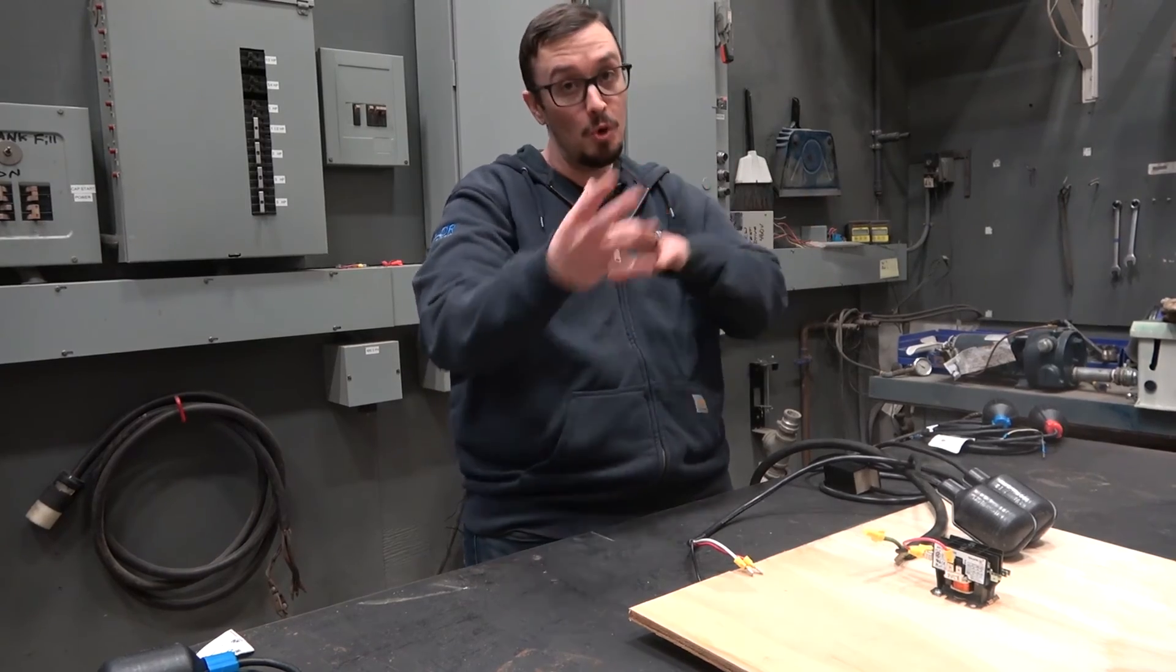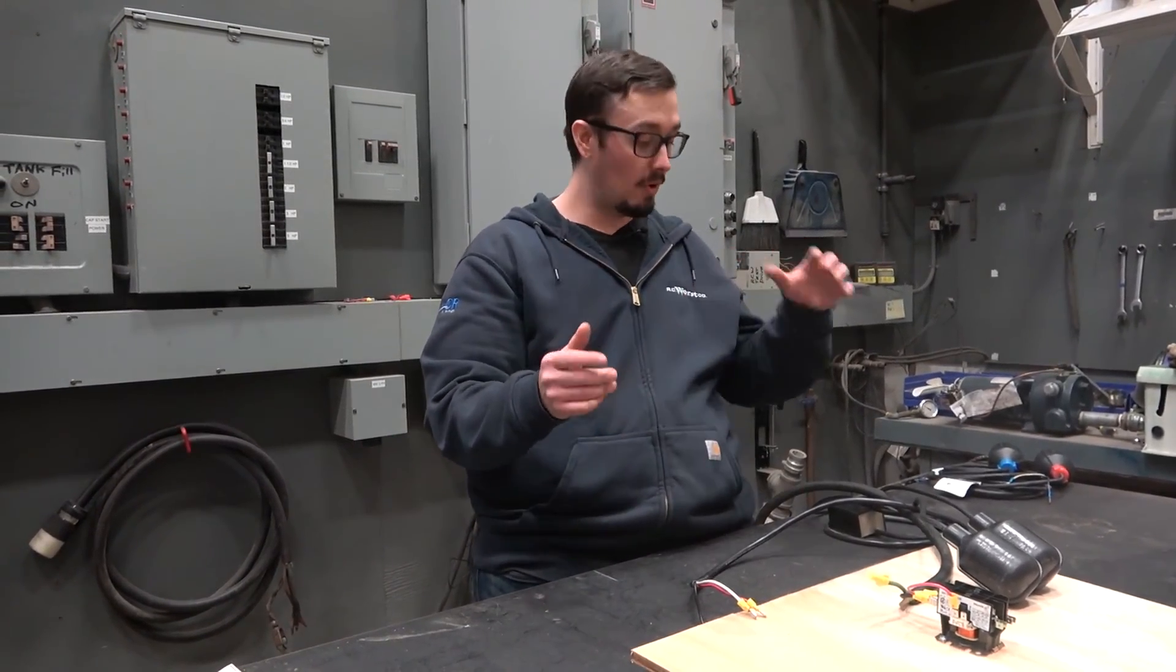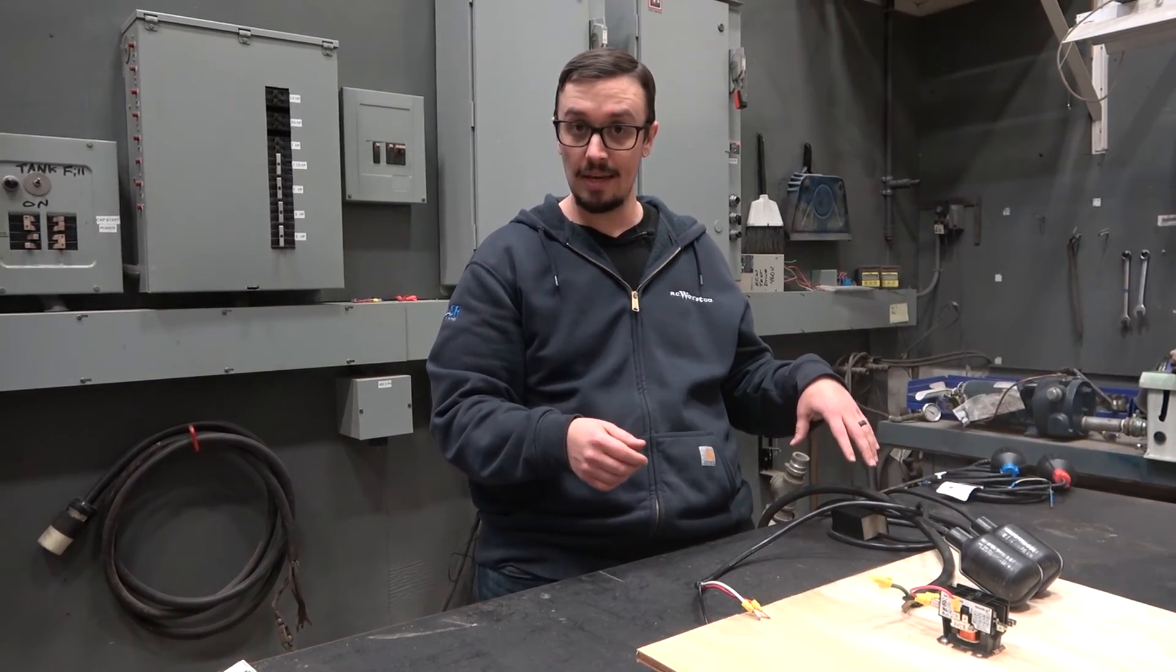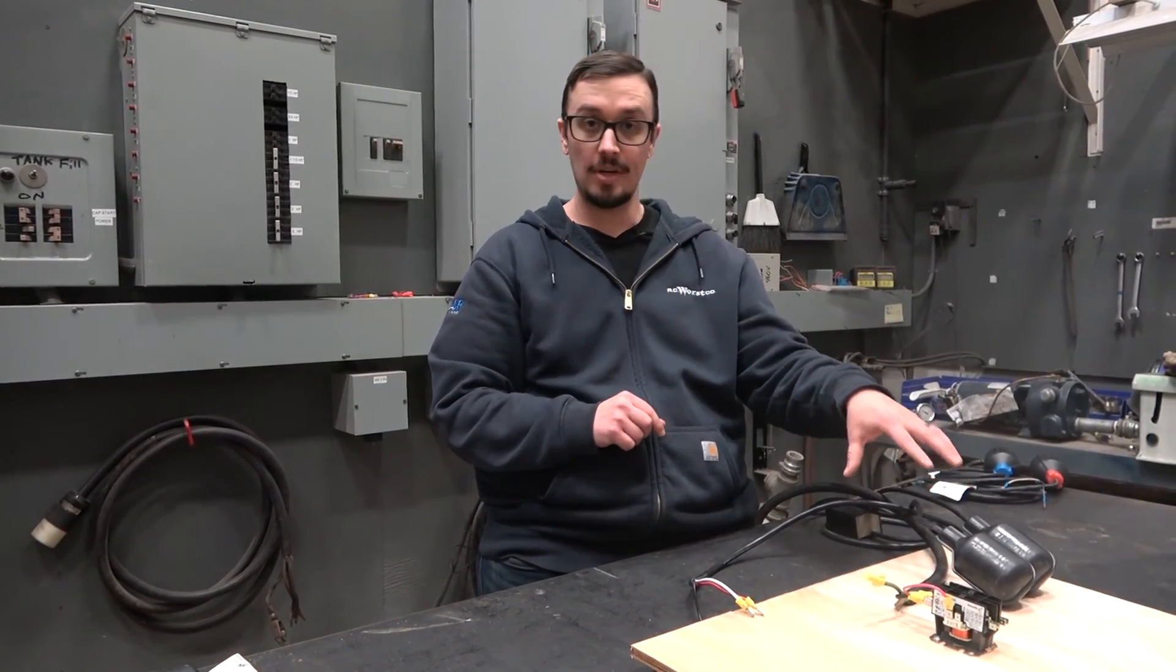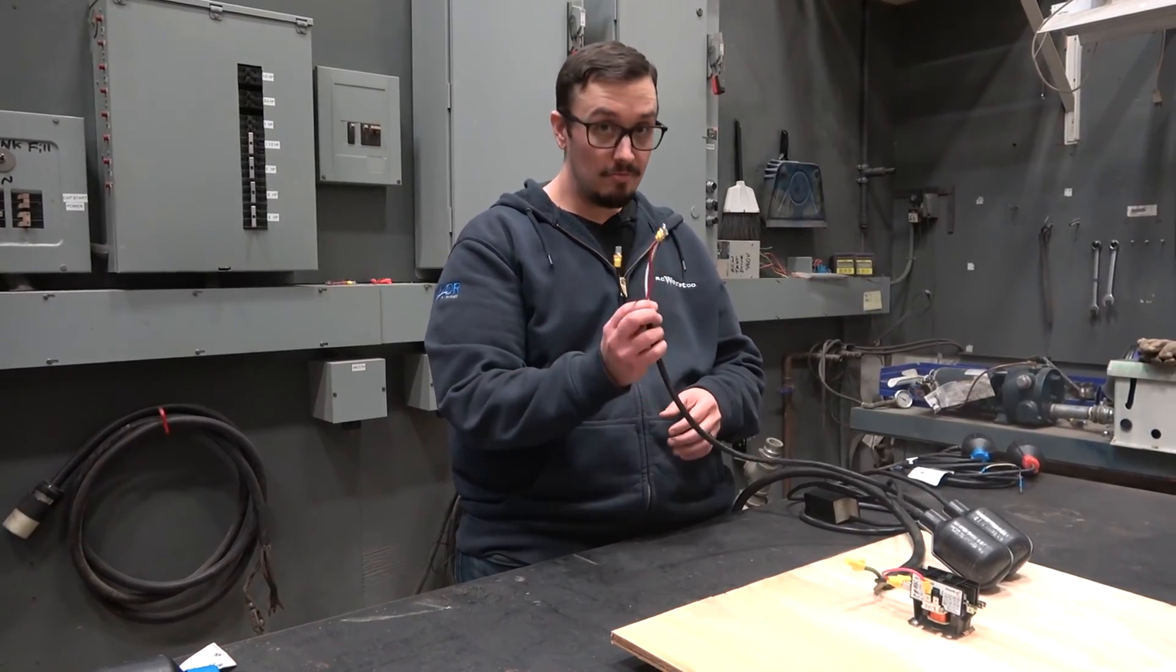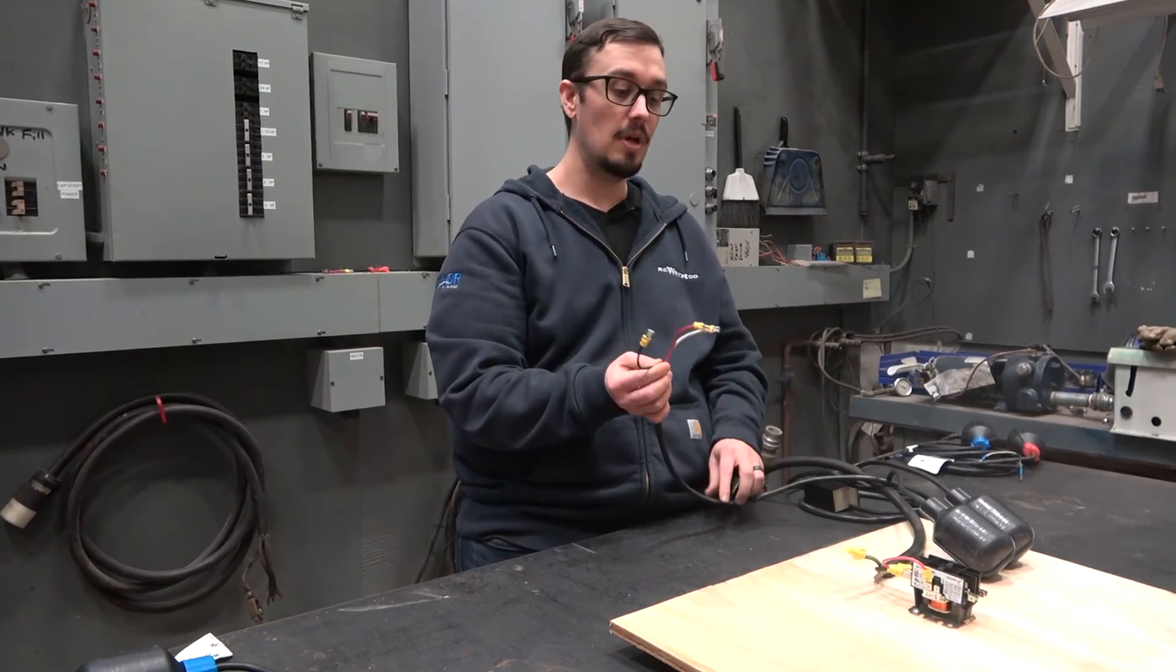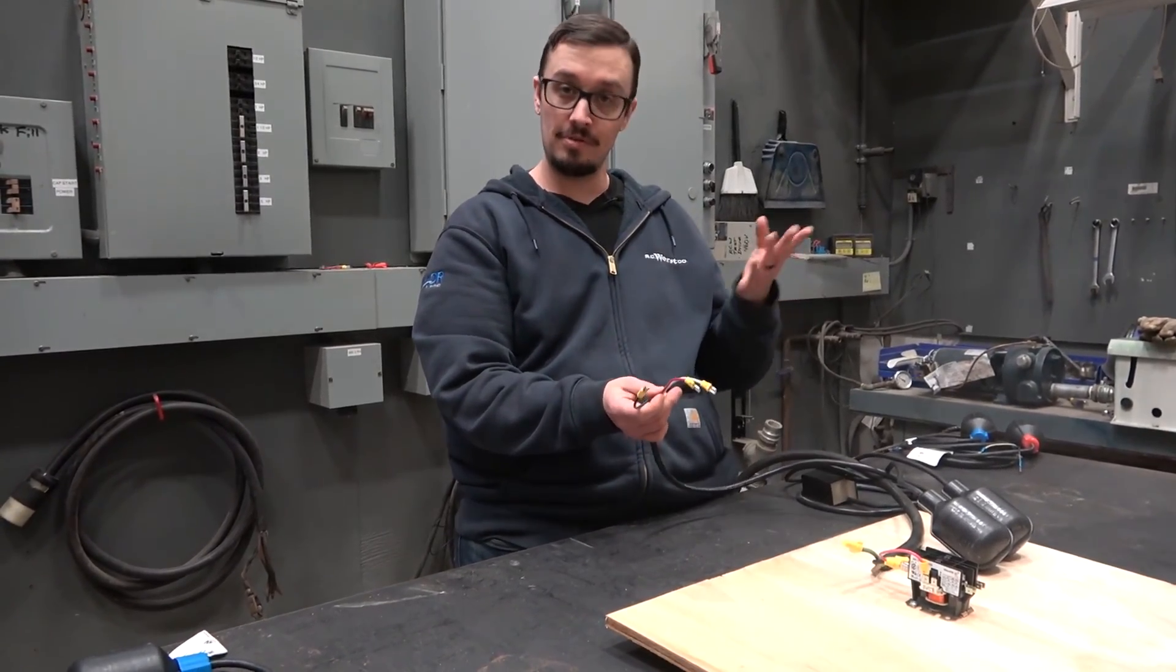We're doing a single float setup as well as two floats, not to be confused with a double float, whereas the double float has a built-in relay that creates a holding circuit within the action of the floats itself, which is why double float switches have three wires instead of your typical two. So the wiring on this one's a little different.